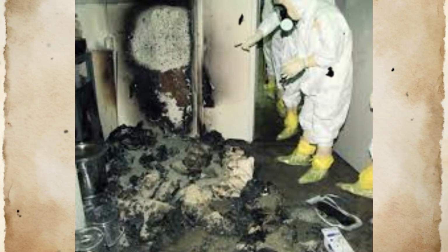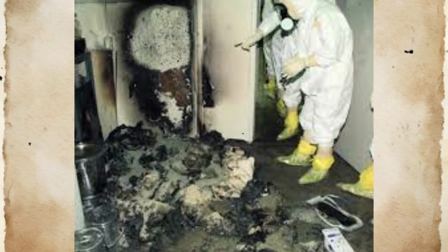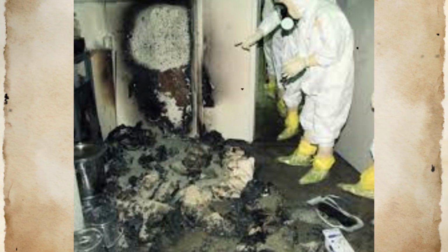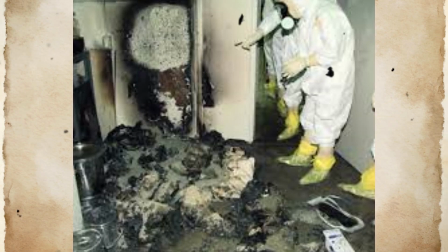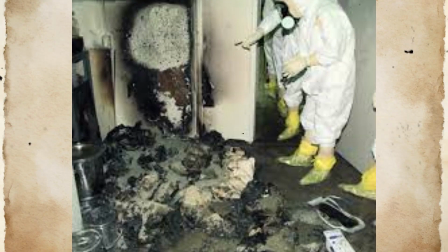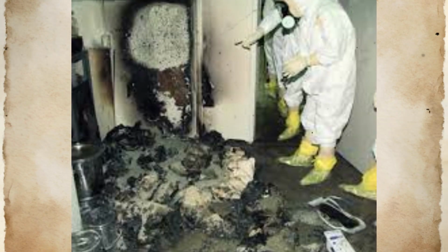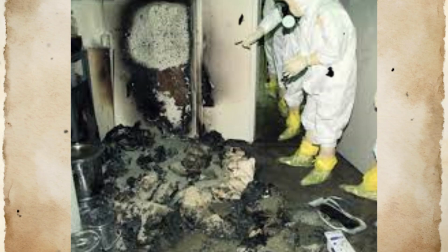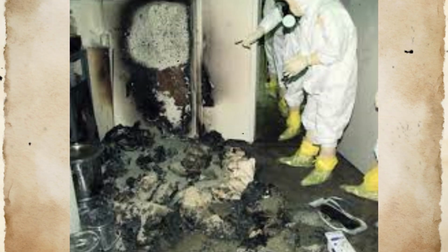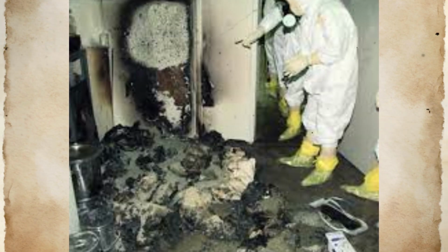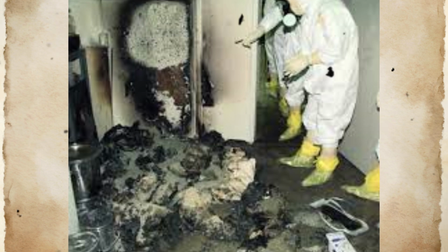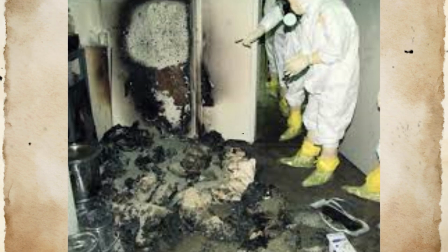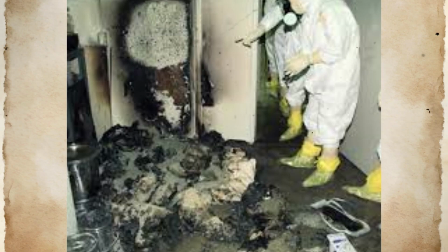Yet this component-focused maintenance philosophy inadvertently obscured system-level vulnerabilities. The maintenance records for emergency generators documented excellent reliability statistics, but these statistics assumed that the electrical distribution panels, cooling water systems, and physical structures supporting the generators would remain functional during emergencies.